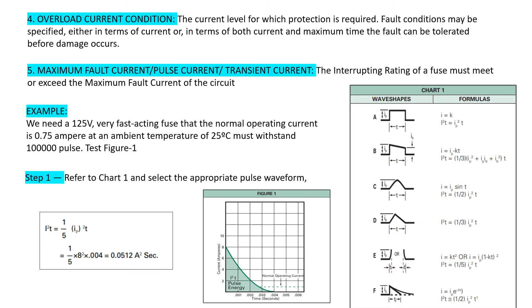First you have to determine the required value of nominal melting I square T by referring to chart 2. As you see, previously we wanted my device to withstand 1 lakh pulses of the fuse. If it is 1 lakh pulses, then pulse I square T is equal to 22% of nominal melting I square T. So nominal melting I square T is equal to pulse I square T divided by 0.22. So we get nominal melting I square T as 0.2327 ampere square seconds.